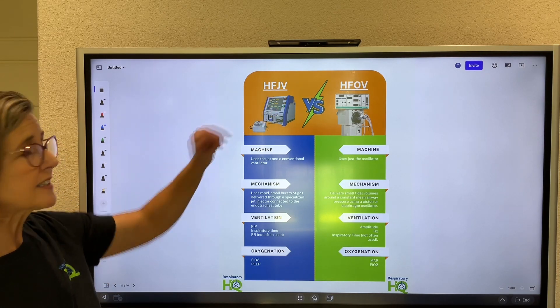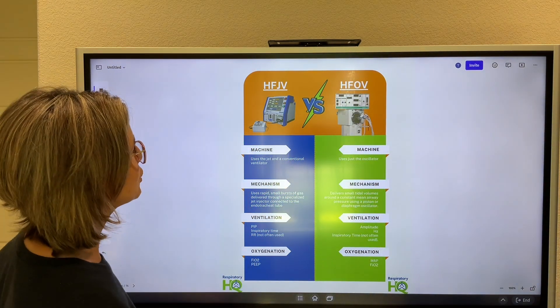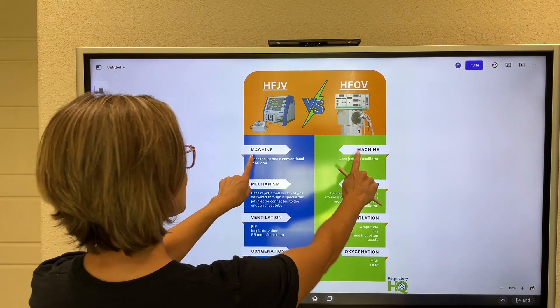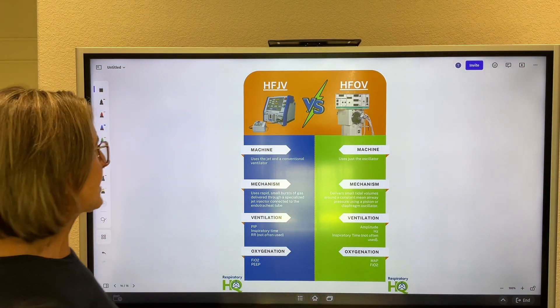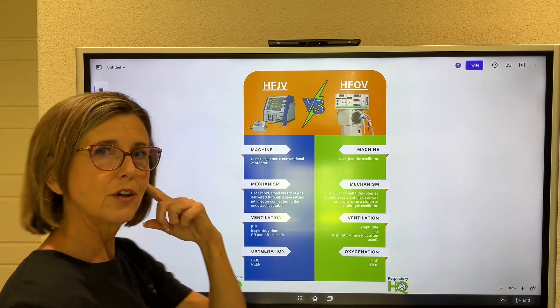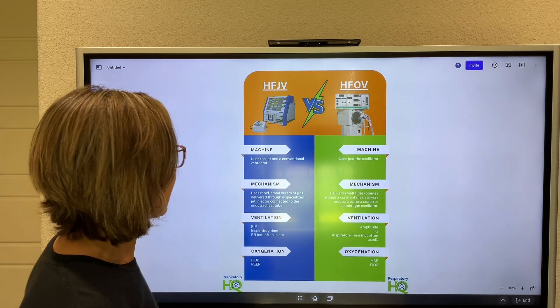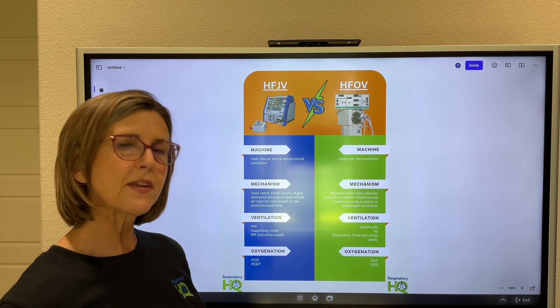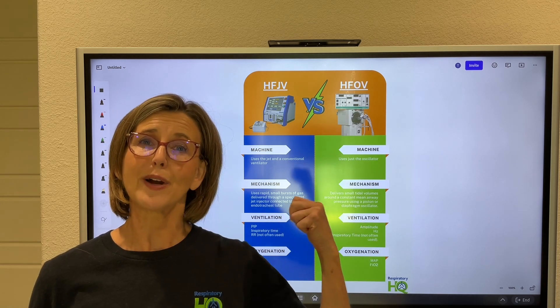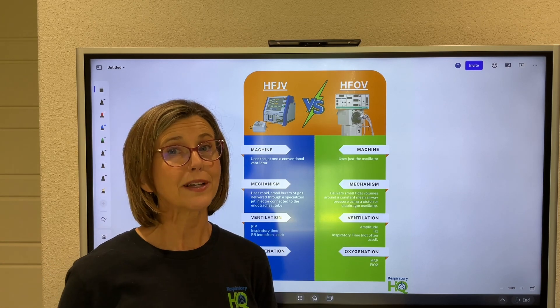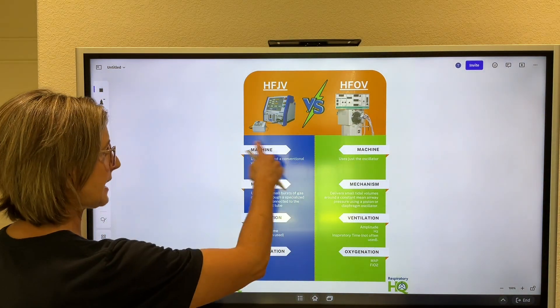There are two ways to do high frequency ventilation: high frequency jet ventilation with a jet ventilator, or high frequency oscillatory ventilation. I'm going to compare each type according to the machine, how they work, and how you adjust for ventilation and oxygenation. For high frequency jet, you have to use two different machines — the jet ventilator and a conventional ventilator. The jet ventilator is responsible for the peak inspiratory pressure, while the conventional ventilator provides continuous flow, FiO2, and PEEP.